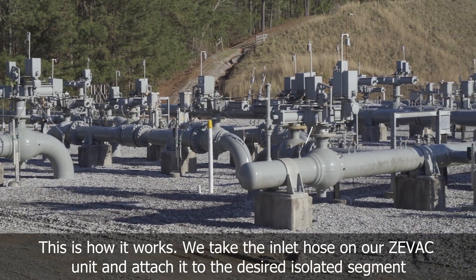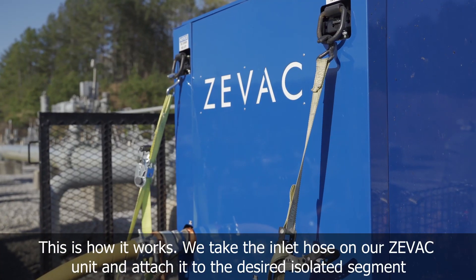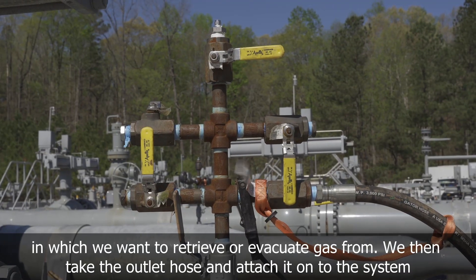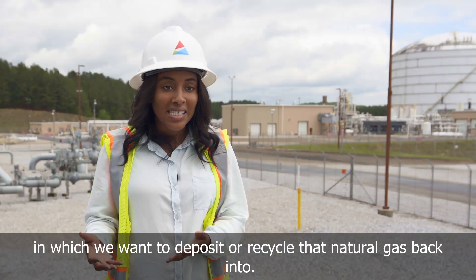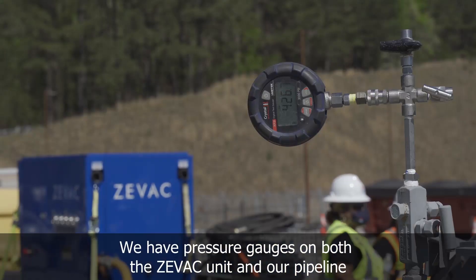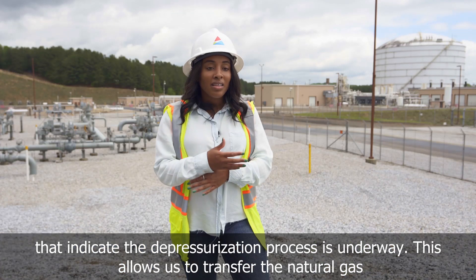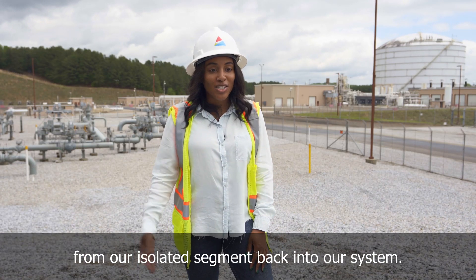This is how it works. We take the inlet hose on our ZEVAC unit and attach it to the desired isolated segment from which we want to retrieve or evacuate gas. We then take the outlet hose and attach it onto the system in which we want to deposit or recycle that natural gas back into. We have pressure gauges on both the ZEVAC unit and our pipeline that indicate the depressurization process is underway. This allows us to transfer the natural gas from our isolated segment back into our system.